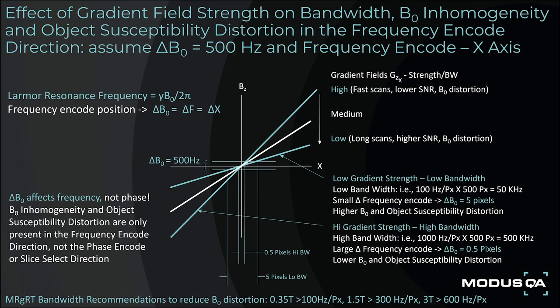In the example noted, a B0 perturbation equivalent to 500 Hz is assumed in the frequency encode direction. Scanning at 100 Hz per pixel and then 1000 Hz per pixel bandwidth is compared, showing B0 perturbation-related distortion is reduced from 5 pixels to 0.5 pixels. Recommendations for MRGRT scanning are bandwidth minimums of 100 Hz per pixel at 0.35 T, 300 Hz per pixel at 1.5 T, and 600 Hz per pixel at 3 T.